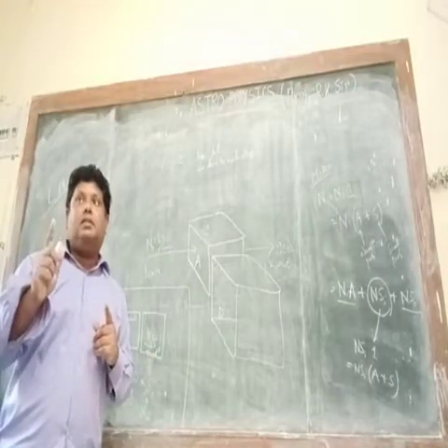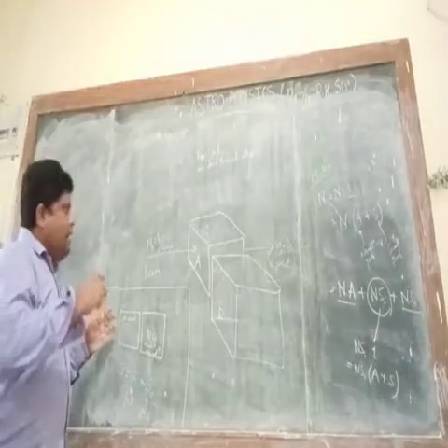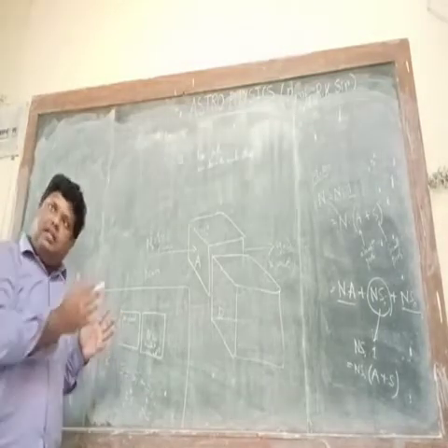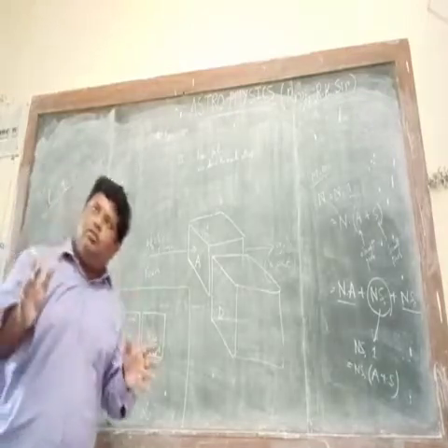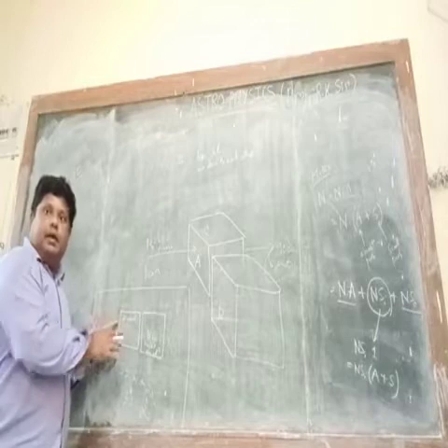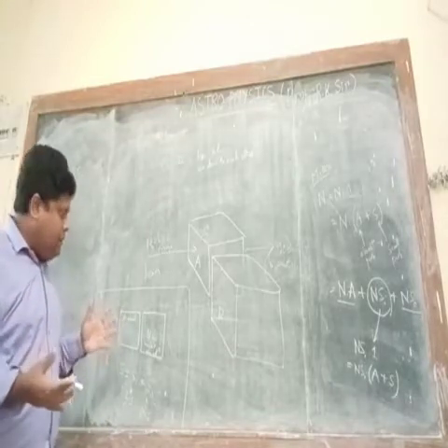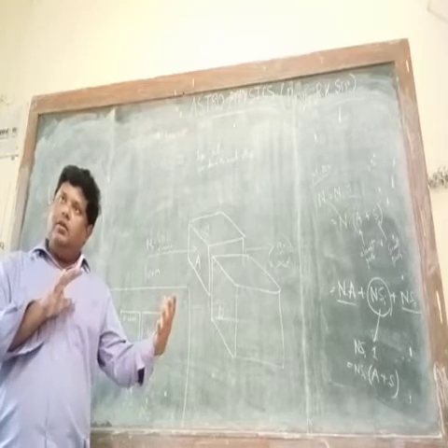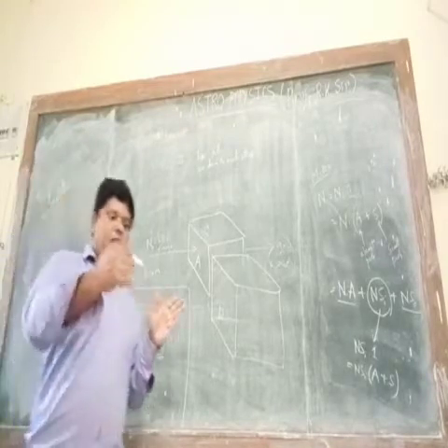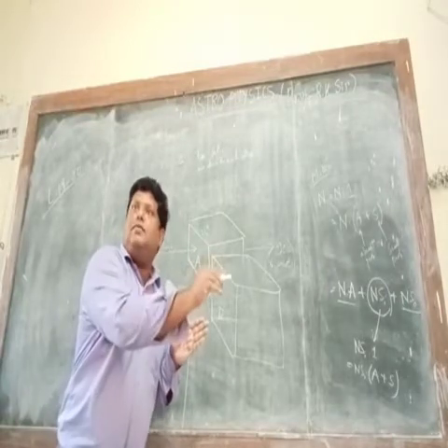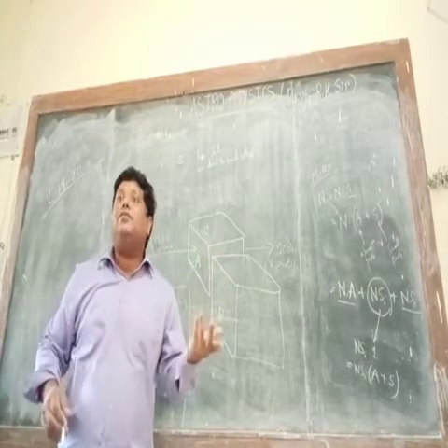What is the catch? The catch is that I am approximating right now a cube detector. All sides are equal, and for isotropic scattering, when all sides are equal, there is no problem. But suppose this is not a cube. This is a cuboid. As a result, when the gamma ray enters this part, it sees a different volume, and when it scatters from the side, it sees another different volume.